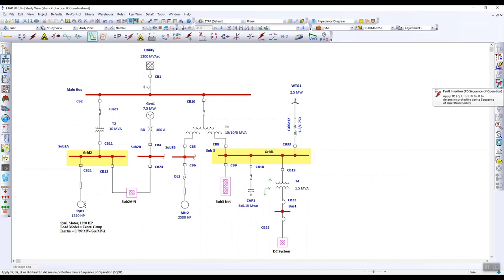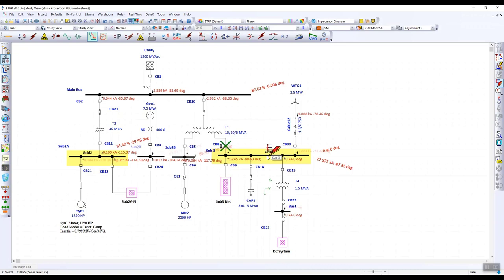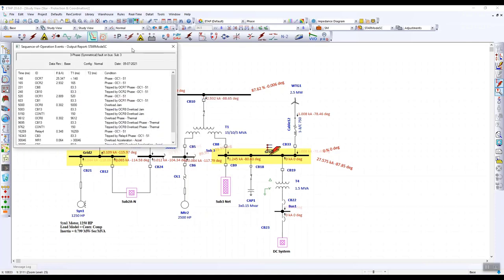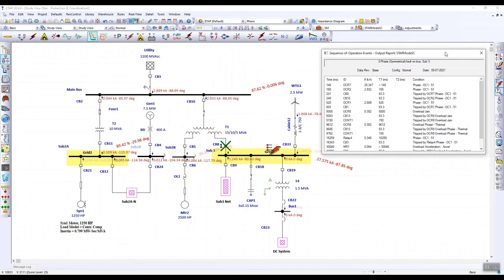Let's take a look at sequence of operation. So this is a fault insertion tool, where when we add a fault to our project, we will see an animation that provides the order in which our protective devices will trip. This viewer shows a summary of which device tripped first, and it goes down the list sequentially. It shows at what time each device tripped, how long it tripped for, and the condition.